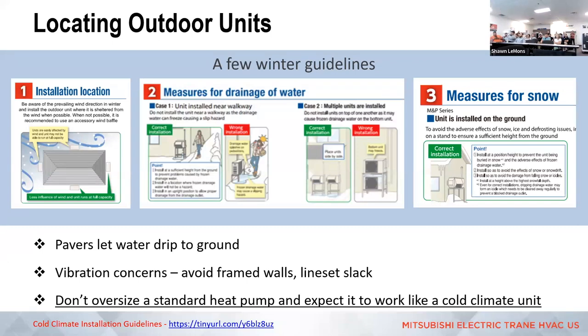For applications in cold climates, where can you put these outdoor units? You wouldn't want to put one on a walkway, because that cold surface collects moisture, frost, and snow, which condenses, and then during defrost that water drips down and refreezes into an ice patch. You don't want to mount units one over the other either, because the lower one suffers from water dropping down and freezing on it.